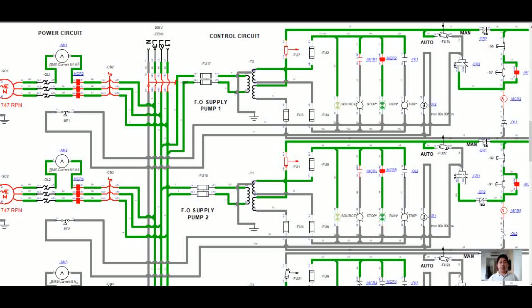It is up to the engineers to decide which pump to keep in service. Normally, our practice on board ship is to change over from pump number one to pump number two every month. When we change the logbook on the first day of the month, we also change the auxiliary pump in service. This habit ensures the proper rotation of usage of the auxiliaries so that the running hours are equalized for the purpose of overhauling — to maximize and utilize each auxiliary.